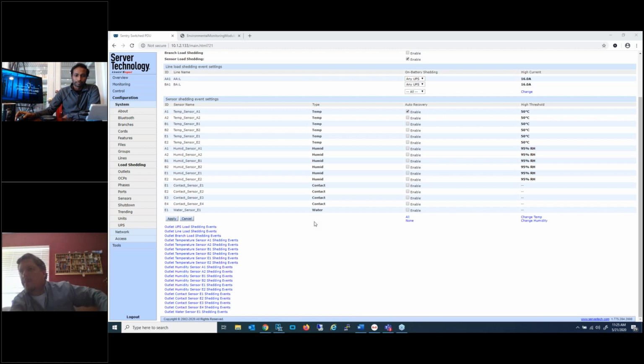Well, not when the load is high. As far as load monitoring, we only have the ability to shed the load, to switch things off on load, that is amperage through the circuit breakers or through the line. But for temperature and humidity, temperature would be the best example. We added the option to switch outlets on due to a request by a large customer, for the very reason that they had fans in the cabinet doors that they didn't want to run constantly, but in the event of temperature exceeding a threshold or multiple thresholds, they were able to automate switching one fan on and then another fan on to increase airflow to assist with cooling rather than switching the device off.